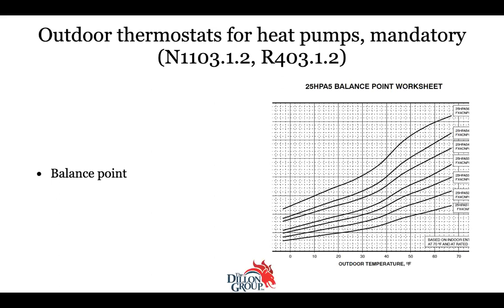Now, what is it set at? 40 friggin' degrees. Why? Because the HVAC contractors apparently have never seen this sheet that comes from the manufacturer, and it comes in all the documentation that they get whenever they want to install a unit. They get a whole bunch of manufacturers' data to help them do the job right. Balance point worksheets is one of them, but they've never seen it. At least that's what they tell me. They didn't know these things existed.